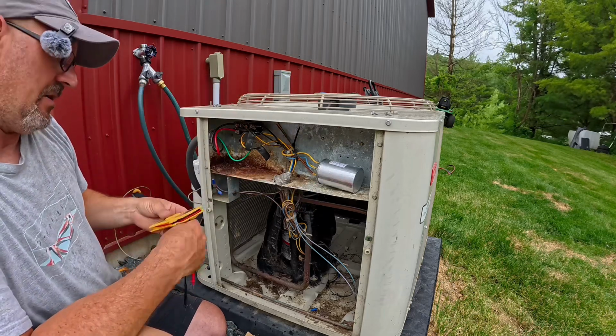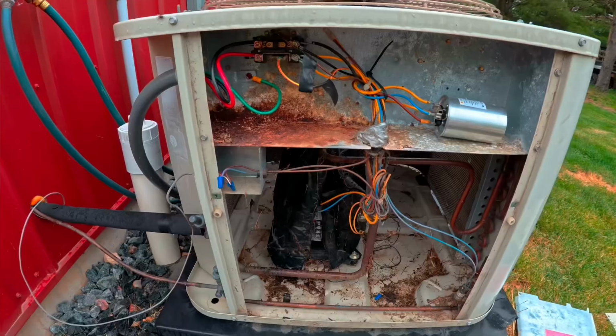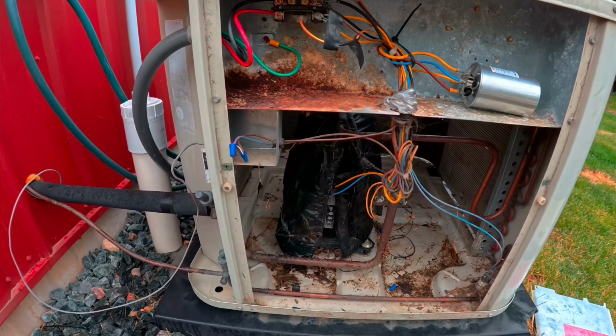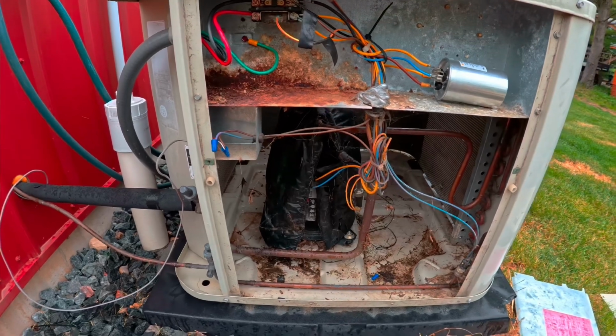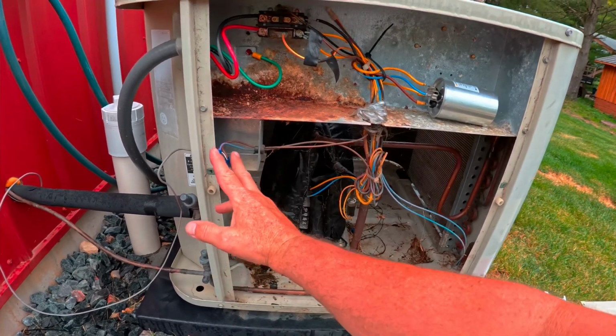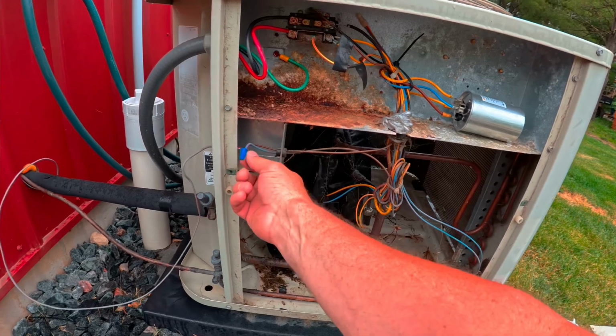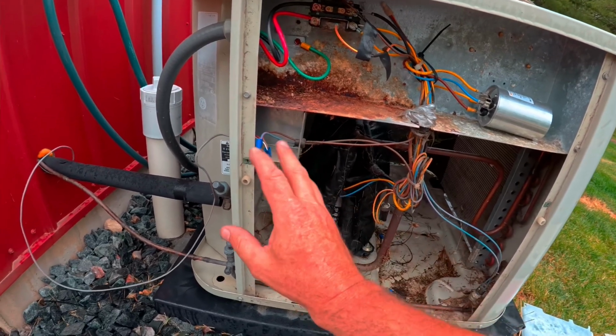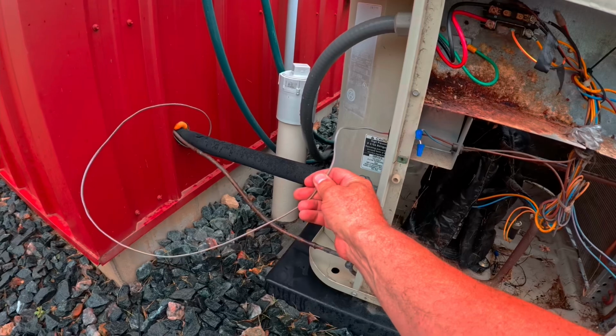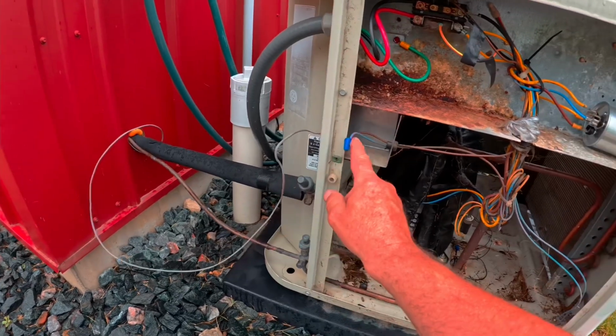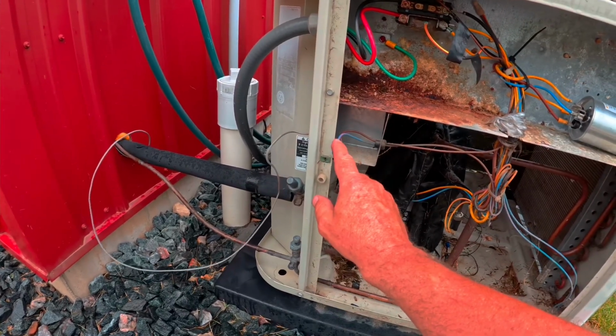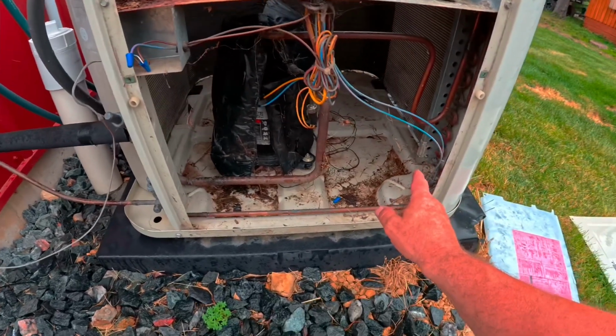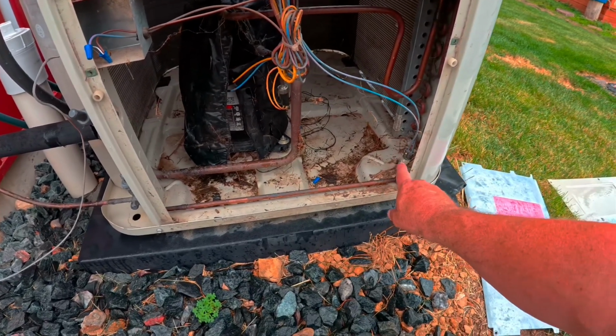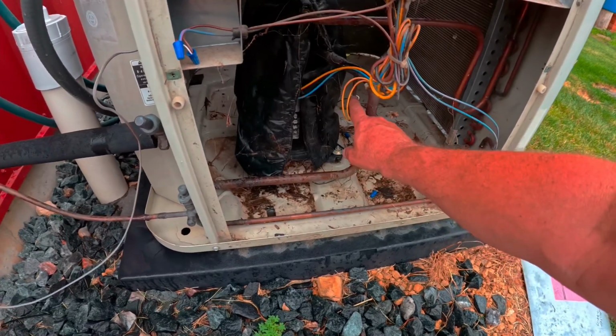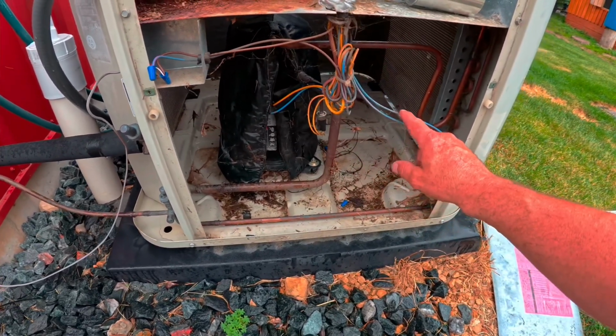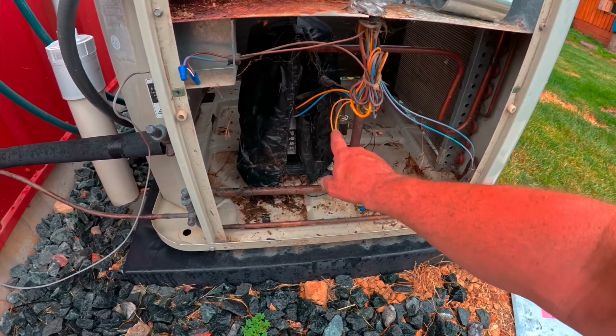So now we're going to check, like I said, the unit's not turning on. So once we're inside the unit, we need to verify where our voltage problem stops at. So we have 24 volts coming in from our thermostat. Right here are my connections. Every unit's going to have a connection somewhere in it where our thermostat wire coming from the thermostat into the AC unit is going to send 24 volts through the control circuit, which in my situation, I have a high pressure switch and I have a low pressure switch.